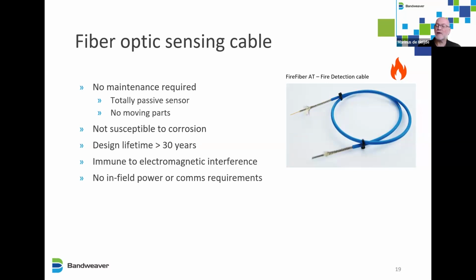Again, it's immune to electromagnetic interference and also radio frequency interference, and there is no in-field power or comms required. It's also very lightweight and flexible, which makes it easy to install. Just to give you an idea, a kilometer of cable weighs 21 kilograms, easily handled by just one person. Other types of installations, like the electrical linear heat detection we mentioned earlier, have a much higher weight because of all the metal inside. So our cable is very easy to install.